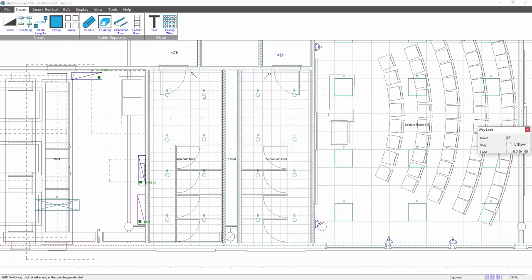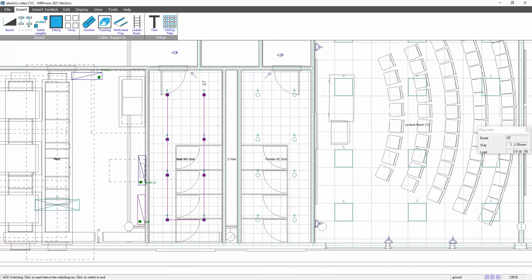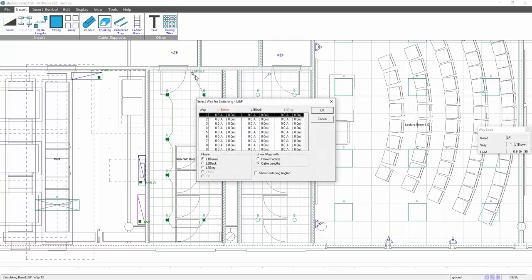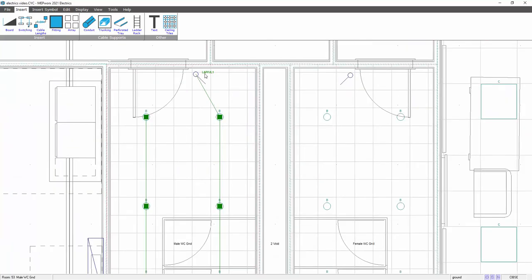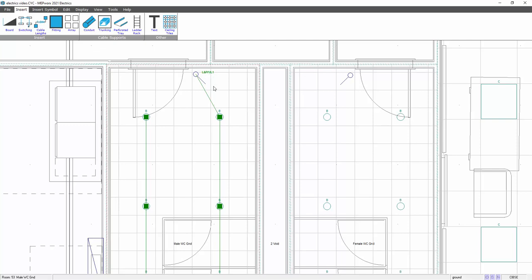And then what I do, I click once on each of my light fittings with one click. This then connects the fittings together, and this will look at the circuit wattages from the lighting database that was used in the lighting program. Click once on the switch, and that then gives me my current rating, 0.9 amps, on that way number one, L1 circuit.